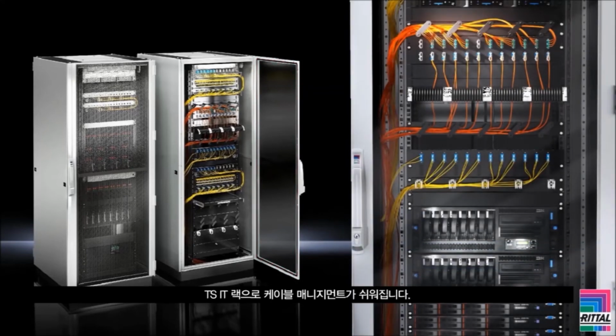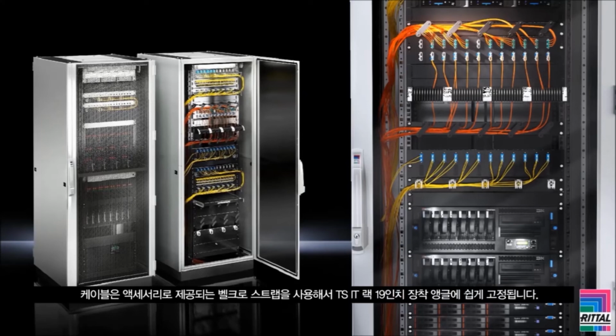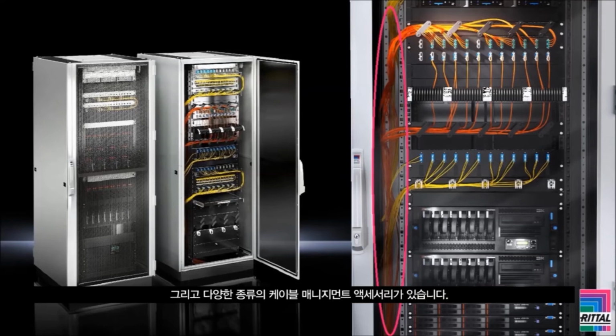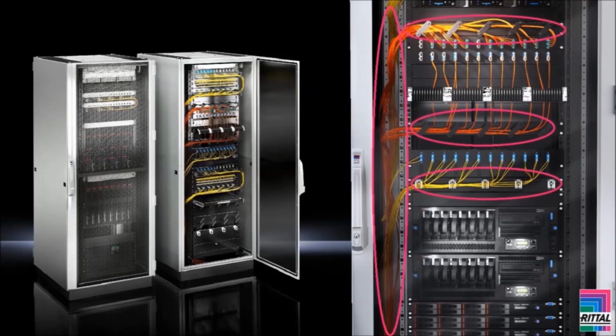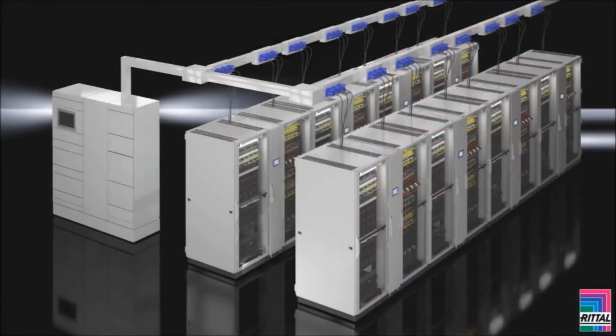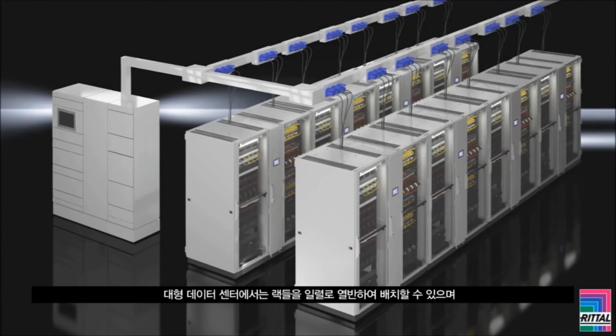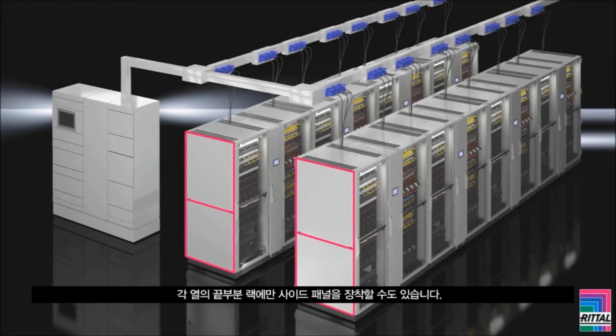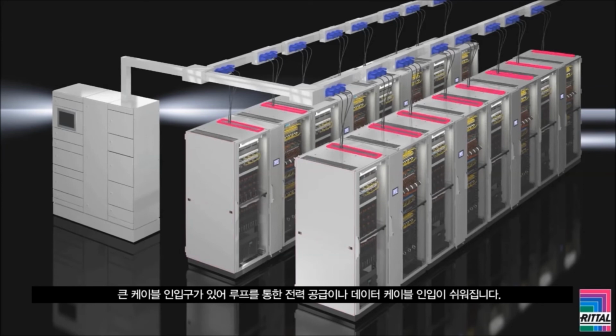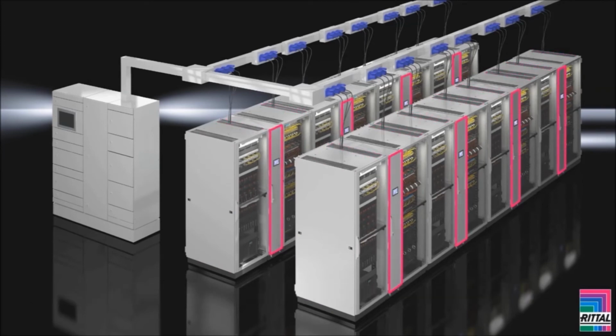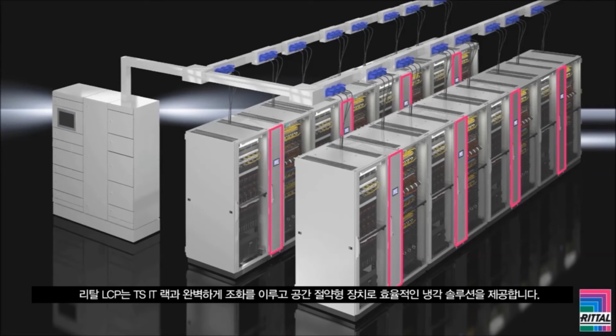Cable management is made easy with the TSIT rack. Cables can easily be secured to the 19-inch mounting angles of the TSIT rack, using Velcro straps, which are provided as an accessory. There is also a wide range of other accessories to help with cable management. In a large data center, where the racks are bayed together in rows, you may only want to fit side panels at the end of each row. Feeding power or data cables through the roof is made easy with large cable entries. The Rittal LCPs are seen mounted in between racks. The Rittal LCP is a perfect match with the TSIT rack, and offers an efficient cooling solution in a space-saving arrangement.